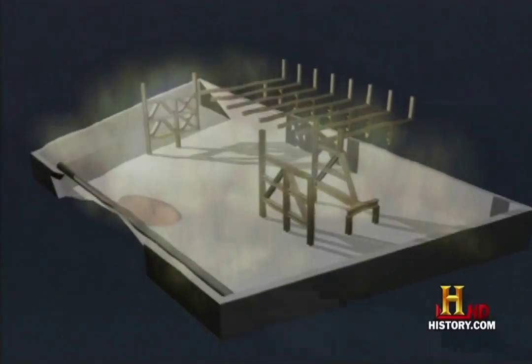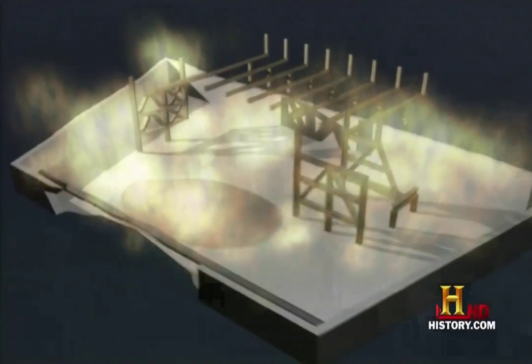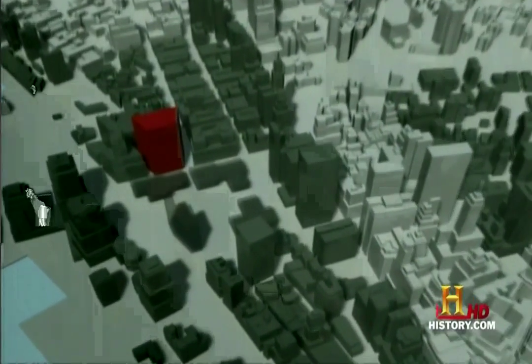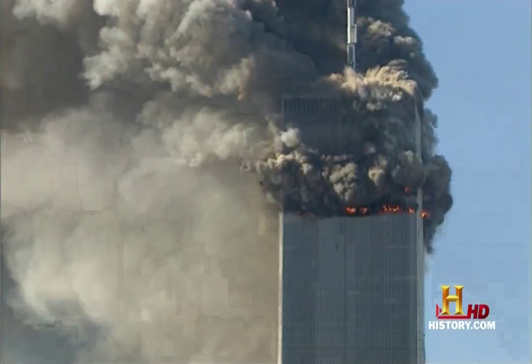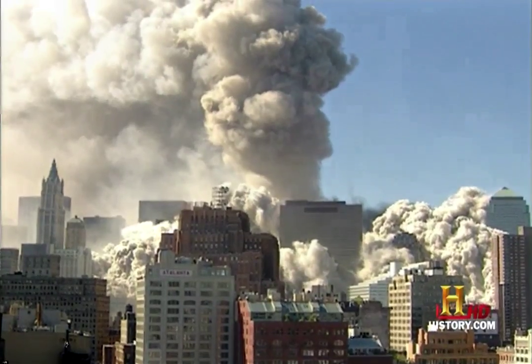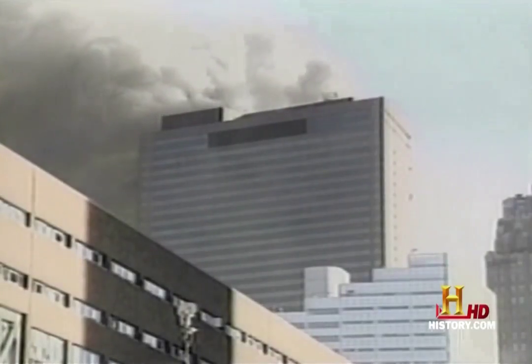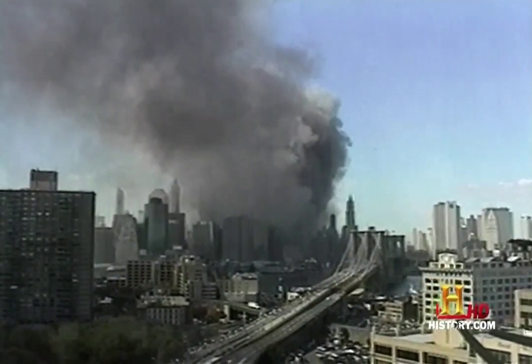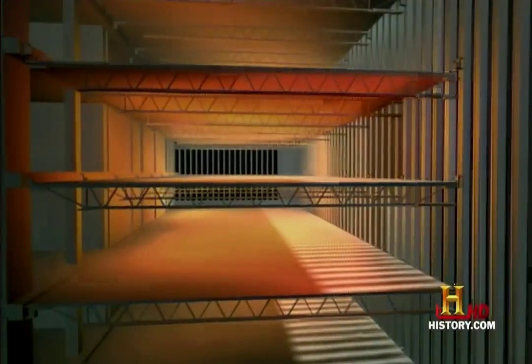One theory suggests the steel around the 5th floor was superheated by diesel fuel discharged from broken pipes, supplying the building's emergency generators. But the explanation may be simpler. The building caught fire at 10:30 a.m. when Tower 1 collapsed. The water pipes supplying the sprinkler systems were also damaged. And the fire department made the decision to allow an evacuated building to burn for the next 7 hours in favor of trying to save the lives of those trapped in the rubble of the Twin Towers. If you allow it to burn long enough, it's going to get past the fireproofing material and it's going to cook the steel, and the steel is going to yield.